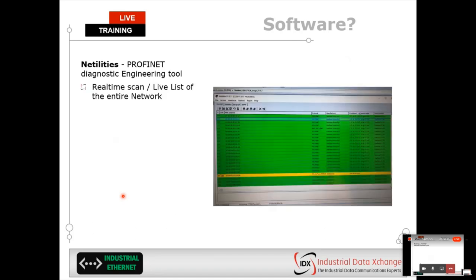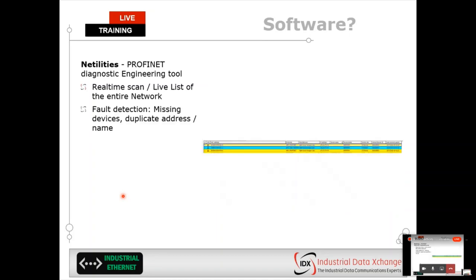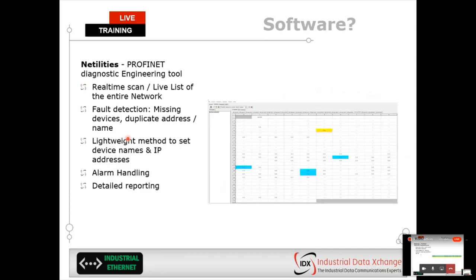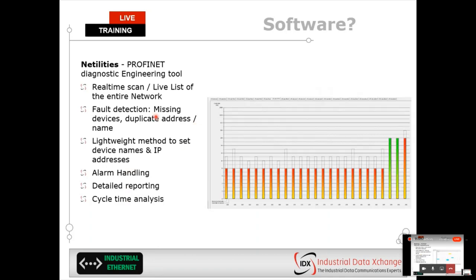There is a lot of engineering specific software. This one, called Netilities, is designed specifically for PROFINET. It does a real-time scan of the live list of the entire network. You can pick up any missing devices, duplicate addresses. PROFINET actually uses device names to communicate, so you can pick up if that's been a problem, alarm handling, and also get detailed reporting. Netilities is also used with a tap connector or a mirror port.